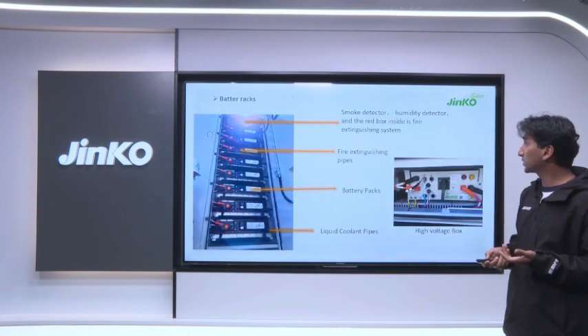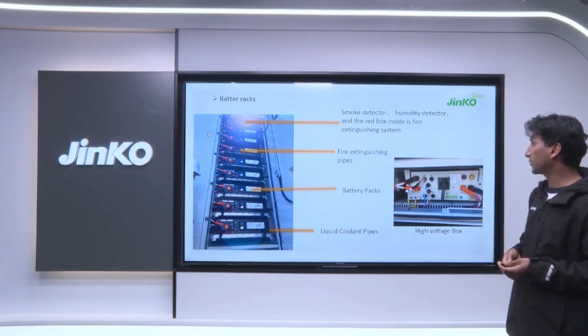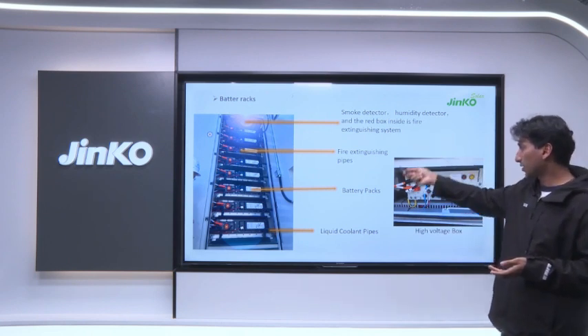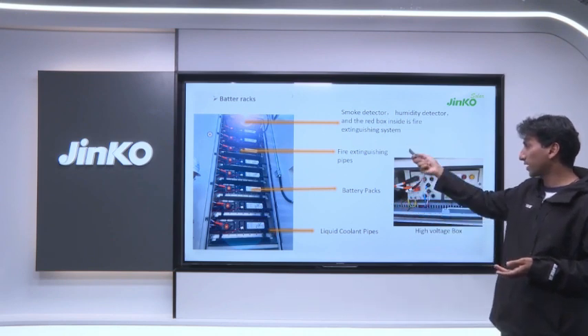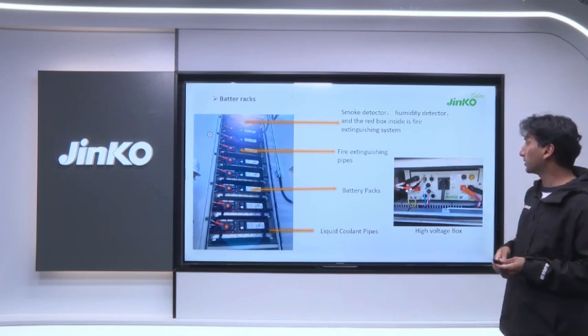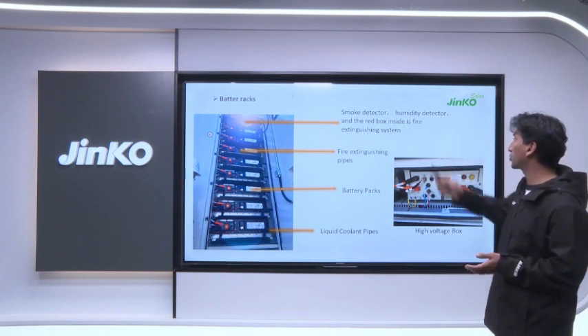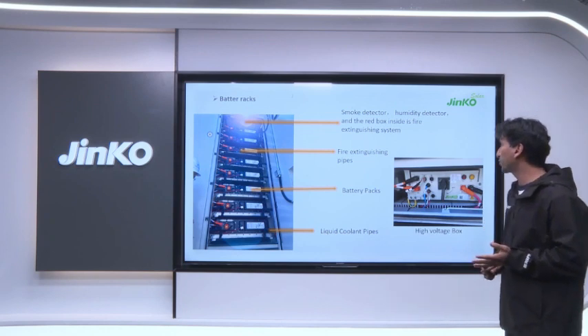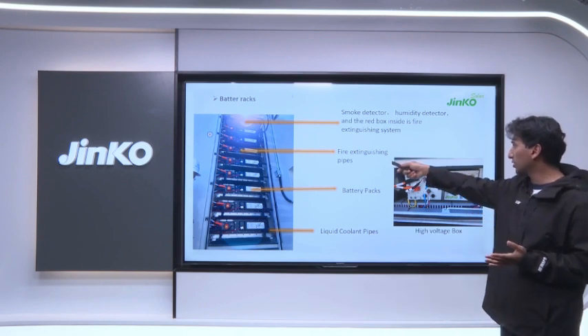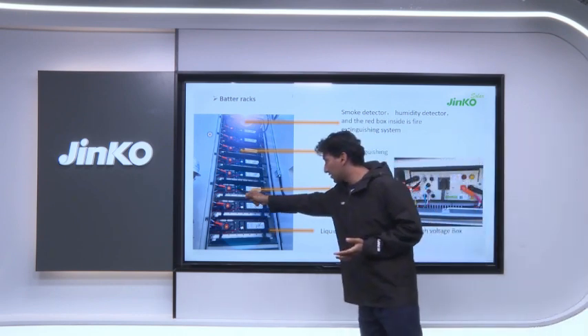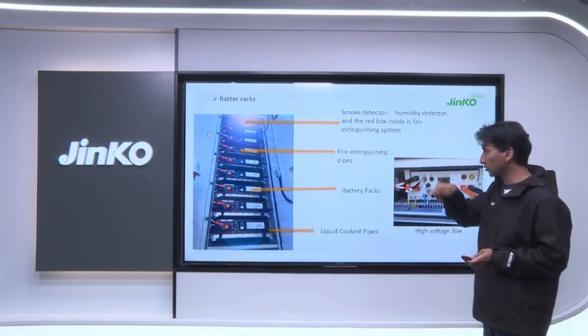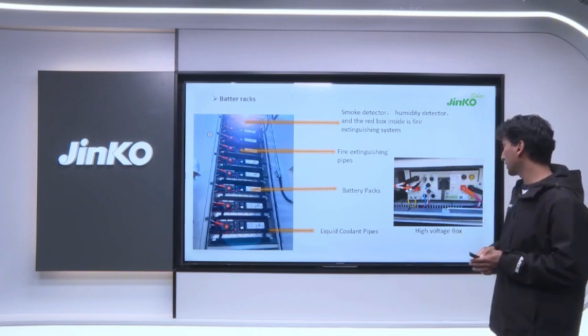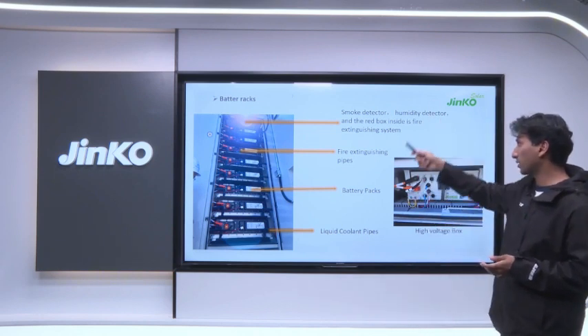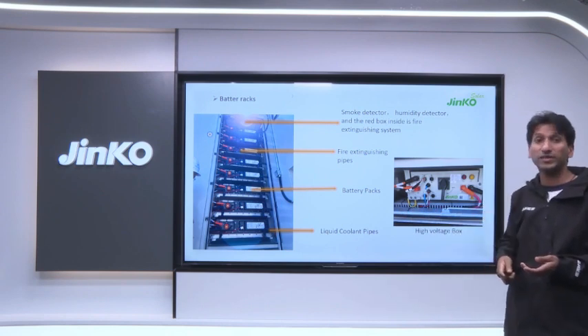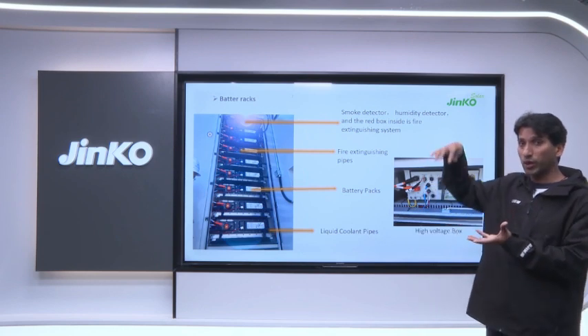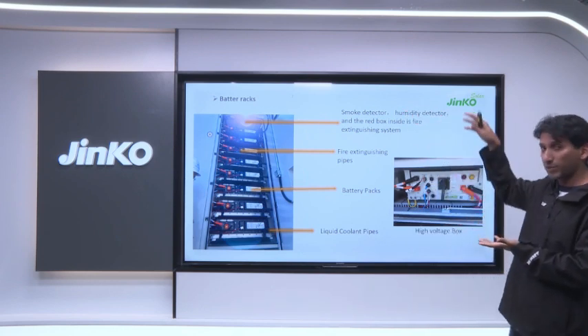This is one of the racks. I've taken a picture of one rack. As you can see, each rack has 8 battery packs, and on the upper side there are smoke detectors, humidity detectors, and the fire extinguishing system. There are fire extinguishing pipes, as you can see on this side, going inside the battery packs. There's also liquid coolant, and each rack has a high voltage box. As discussed in the last video, the high voltage box is the main connecting point between the battery packs, making up one whole rack.